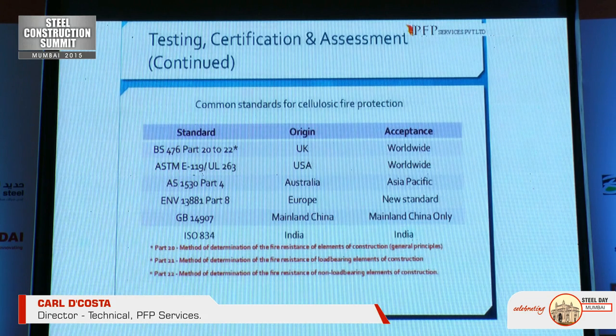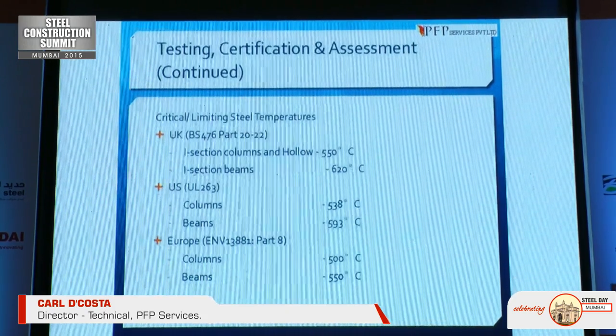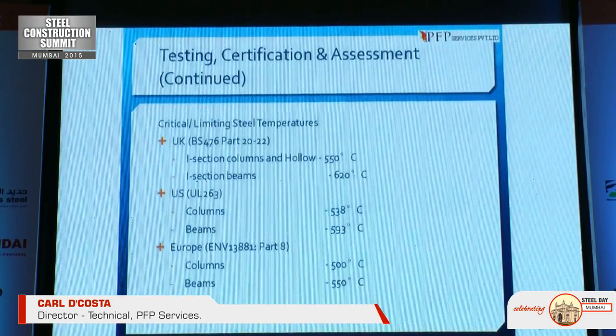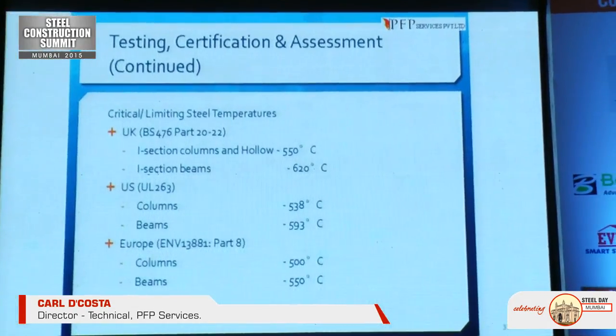For cellulosic fire protection, applicable standards worldwide include British, American, Australian, European, mainland China, and Indian standards. The critical steel limiting temperatures at which coatings are tested and thicknesses are designed to meet failure temperatures: under British/UK standards, the failure temperature for hollow sections and columns is 550°C, while for I-sections it is slightly higher at 620°C. Under US UL263 standards it is somewhat less conservative, while the most conservative is the European ENV standard at 500–550°C. India is currently following UK and US standards. This information is important for architects when designing failure temperature specifications.